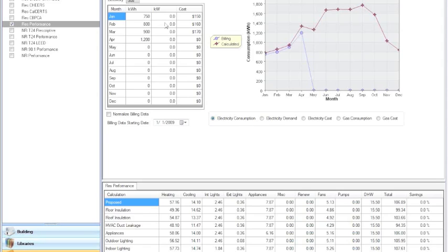The second is you may have legitimate modeling inconsistencies or problems in what you've input into EnergyPro. So you probably want to take a look at things like the duct leakage. Did you do a test in, test out on the duct leakage? If not, then it's anybody's guess as to what's going on there. The building envelope leakage, once again, if you don't have hard numbers there, that's going to be a very hard one to predict. So it could be things like modeling corrections that need to be made.